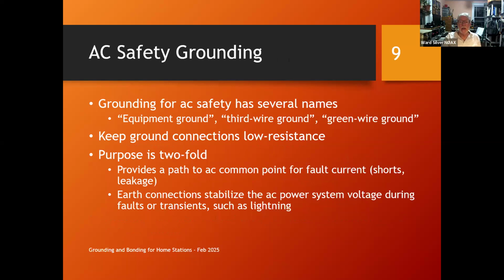AC safety grounding has several names depending on where you live in the country and how old your electrician is. The current preferred term that you'll see in building codes and reference manuals is equipment ground, and that's a connection back to the reference point in your AC power service. It can also be called third wire ground because you've got your hot and neutral, and then you've got the safety ground over here. So that's the third wire. It can also be called the green wire ground because it's usually insulated with green insulation to indicate that it's a ground wire.